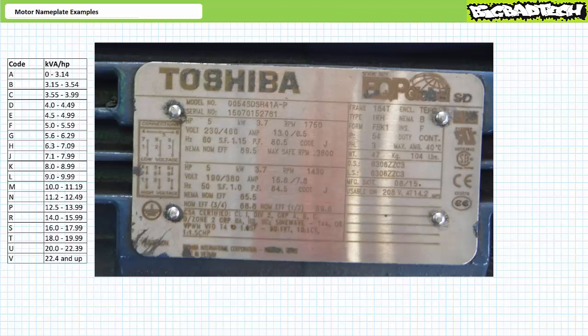There's additional great information on this nameplate including insulation class, temperature data, weight, manufacturing data, and bearing part numbers. LS is the load side (sometimes specified as DE or drive end), whereas OS is the non-load side (sometimes NDE or non-drive end). Lastly, there's all the same data at 50 Hz. If you want another exercise, do this same drill again at 50 Hz. The rated speed at 50 Hz is slower than at 60 Hz, as one might expect.